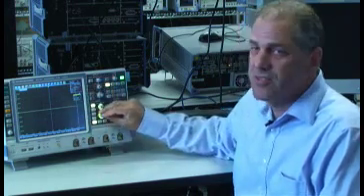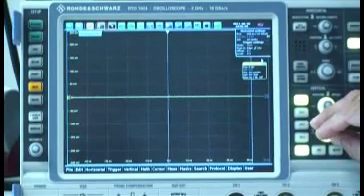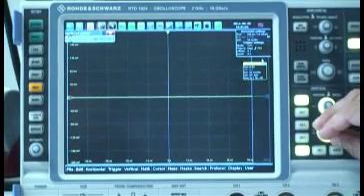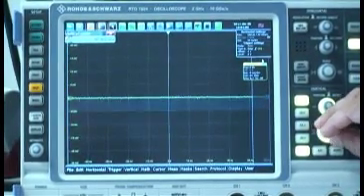So I'm going to adjust the sensitivity range from the current setting, which is 50 millivolts per division, down to 1 millivolt per division.